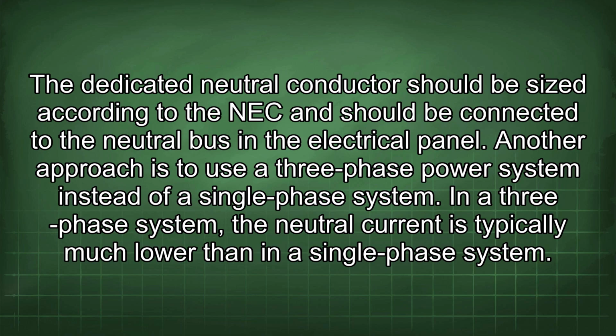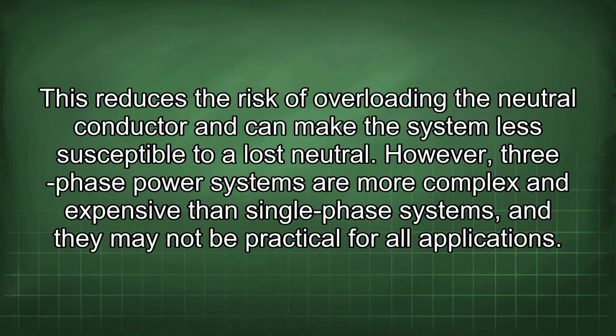In some cases, it may be necessary to install a dedicated neutral conductor from the utility transformer to the building. This provides a redundant neutral path and can reduce the risk of a lost neutral.